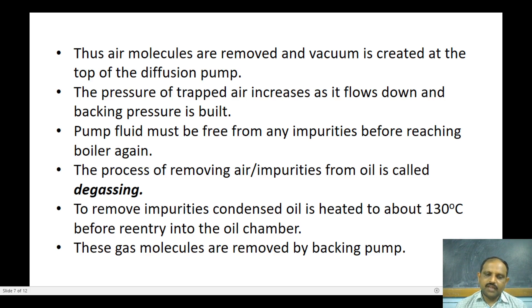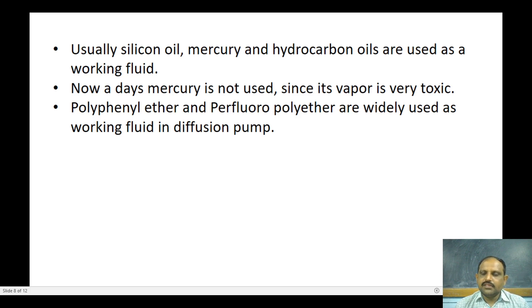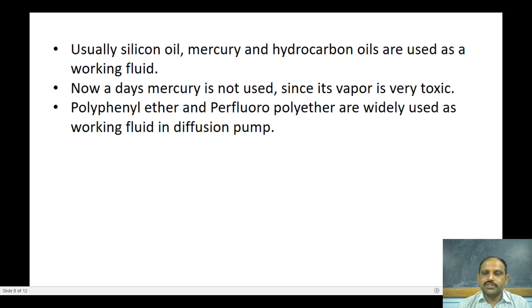Silicon oil, mercury, and hydrocarbon oils are used as working fluids in the diffusion pump. However, mercury is no longer used because it is very toxic — when heated, its vapor is extremely toxic. Polyphenyl ether and perfluoropolyether are now widely used as working fluids in the diffusion pump.